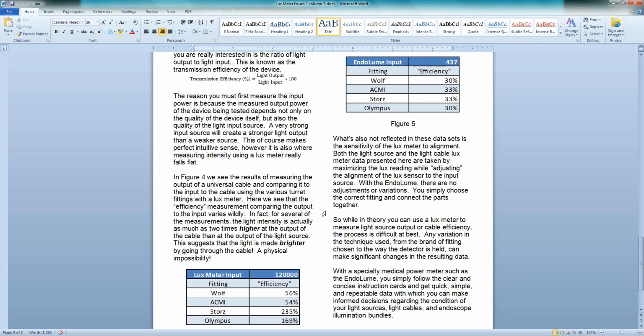By using that variable input from the lux meter, depending on which turret setting you use, you can actually show that the cable is brighter on the output than the input, or dimmer, and it depends which setting you use. With the EndoLume, however, it doesn't matter which setting you use, they all measure approximately the same, 30% transmission efficiency for the cable that I tested in this paper.